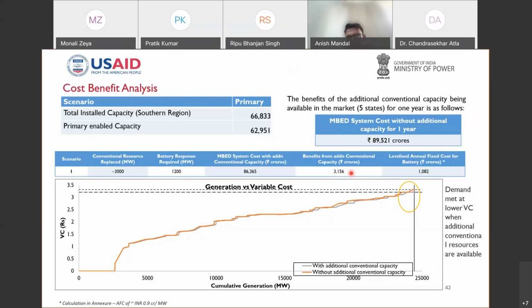So this 3,156 crores, when compared with keeping 1200 megawatt of battery on a standby basis for providing primary reserves, the AFC comes out to be 1,082 crores, or 1,100 crores if you take 0.9 crore per megawatt AFC, which is derived from, for example, a 1 hour battery at 5.5 crores per megawatt. The cost has probably come down 20% lower at today's rate, but even if we take that, the levelized AFC comes out to be 1,100 crores. So the benefit is almost 3 times the cost.